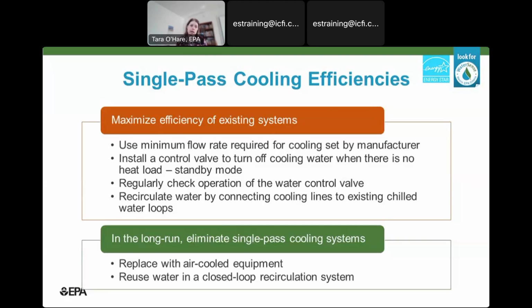So if you can't eliminate it, you want to maximize the efficiency of your system by using the minimum flow rate required by the manufacturer. And you want to install a control valve in it to turn off the water when there's no heat, so that you're putting it in standby mode. And once you have that valve installed, you want to check its operation regularly, because that is something that can stop working, and you may think the system is on standby when it's not. Another thing you can do is recirculate the water by connecting it to existing chilled water loops, if that's possible. Sometimes that depends on the distance between the piece of equipment and the chilled water loop and some other logistical factors.